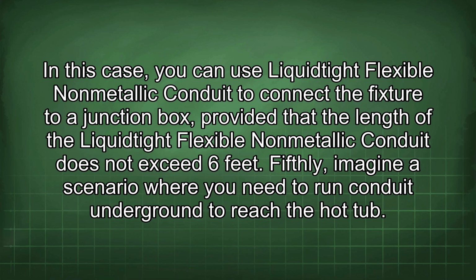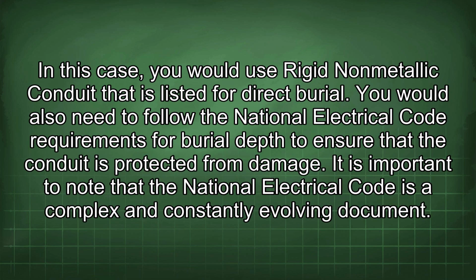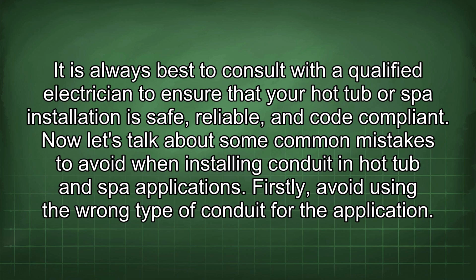Fifthly, imagine a scenario where you need to run conduit underground to reach the hot tub. In this case, you would use rigid non-metallic conduit that is listed for direct burial. You would also need to follow the National Electrical Code requirements for burial depth to ensure that the conduit is protected from damage. It is important to note that the National Electrical Code is a complex and constantly evolving document. It is always best to consult with a qualified electrician to ensure that your hot tub or spa installation is safe, reliable, and code compliant.